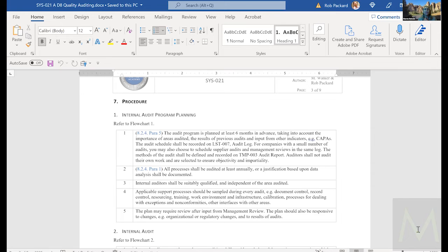The last client I had that was going to the EU with the new product was under MDD. So we created a very similar checklist for MDD, did a traceability to make sure that all of the MDD requirements were met. There are different versions of the ISO 13485 standard. There's an EU version of the standard as well, which has a number of additions in the front because the EU needed to add some stuff. So I just included traceability to all of those clauses and then did a check against the MDD, and that pretty much covered everything.